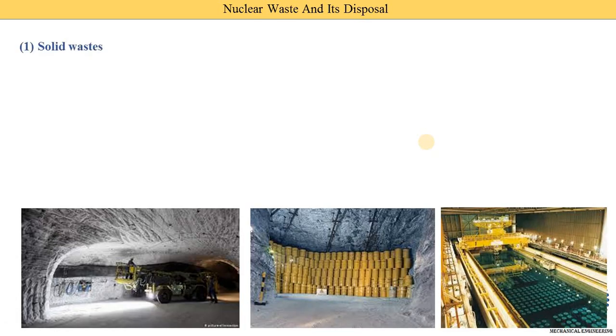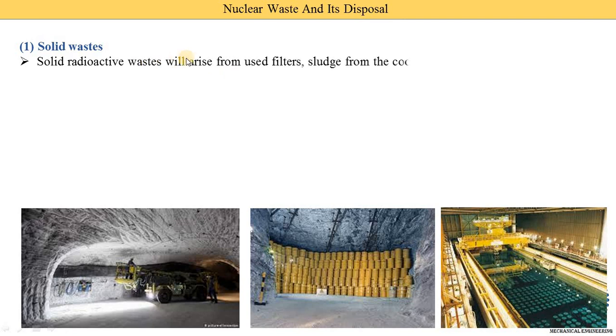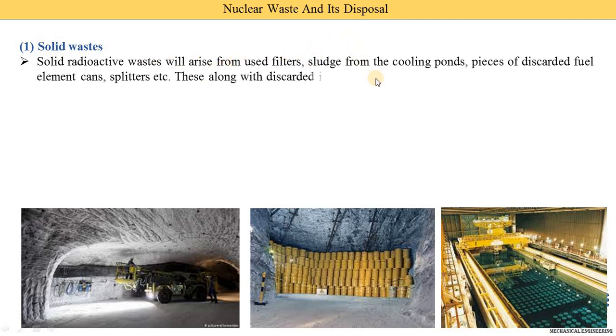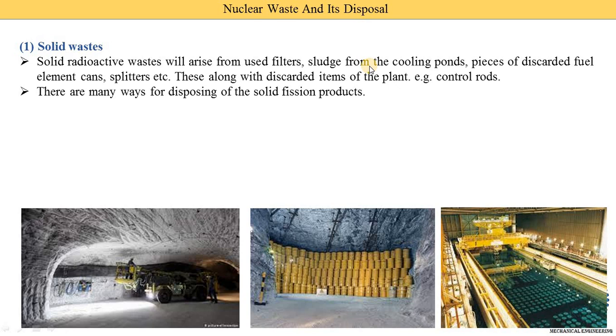First we understand about solid waste — nuclear waste present in the solid state. Solid radioactive waste arises from the use of filters and sludge from the cooling ponds. Pieces of discarded fuel element cans and splitters — the fuel coming out from the nuclear plant — are also waste. Along with discarded items of the plant like control rods, which are components we need to replace after some time, these are the various sources of solid waste.